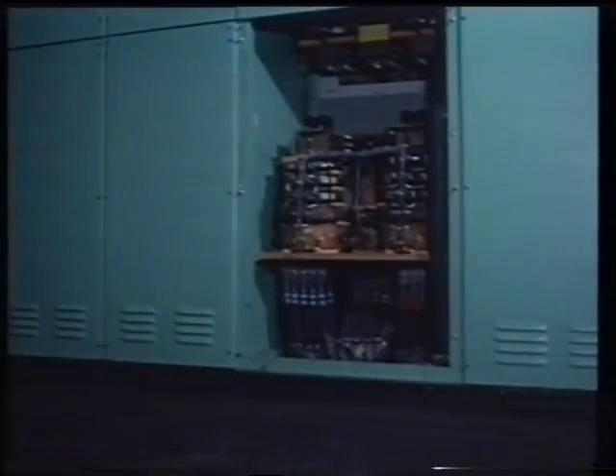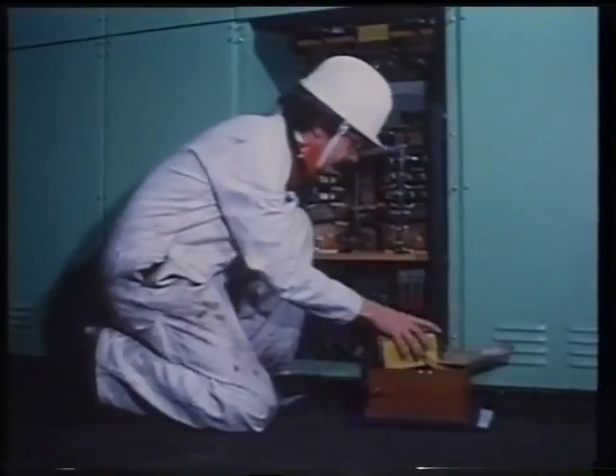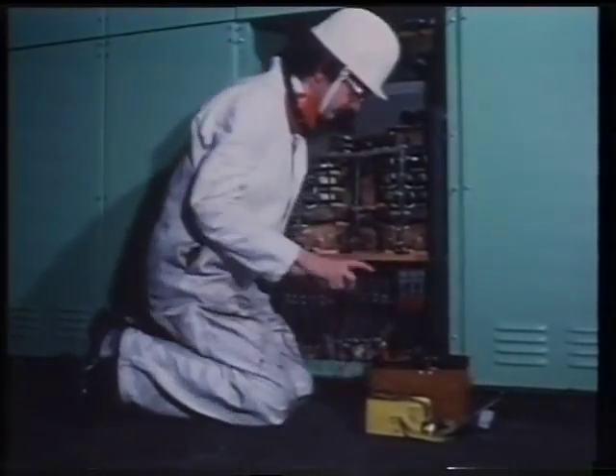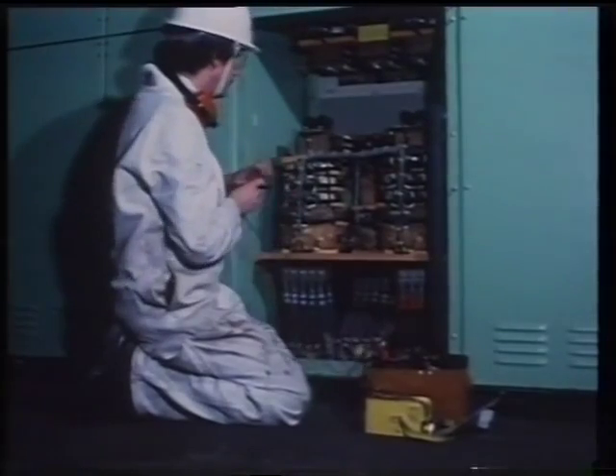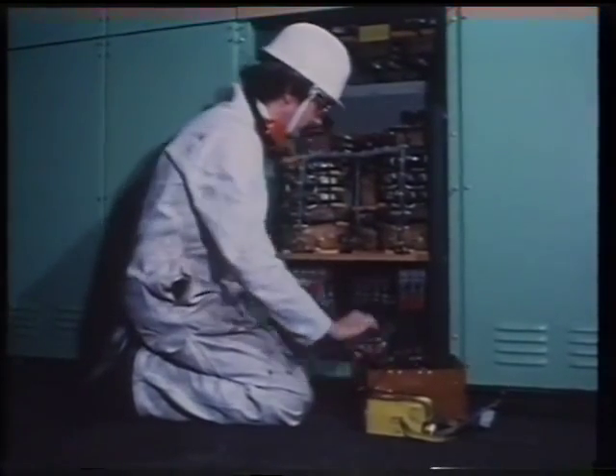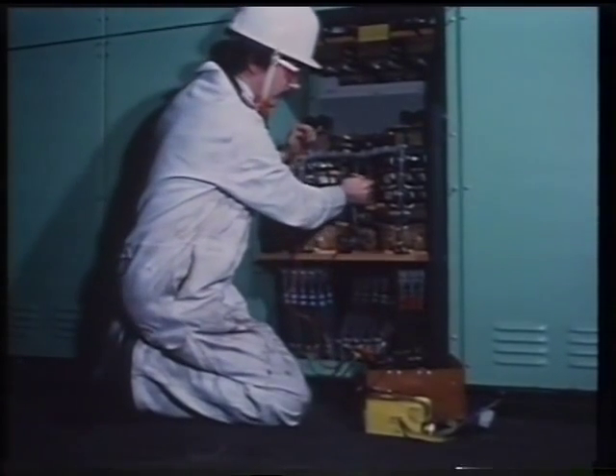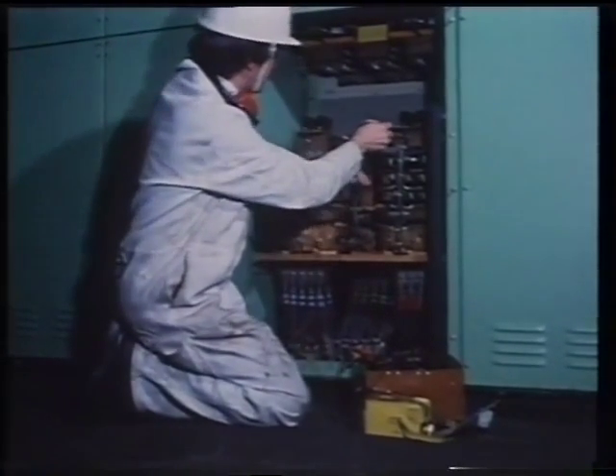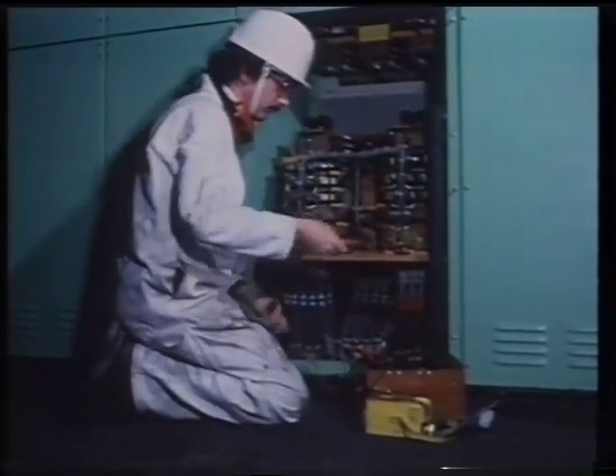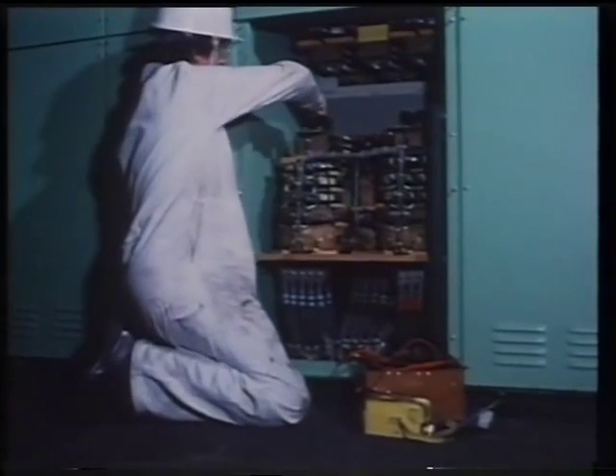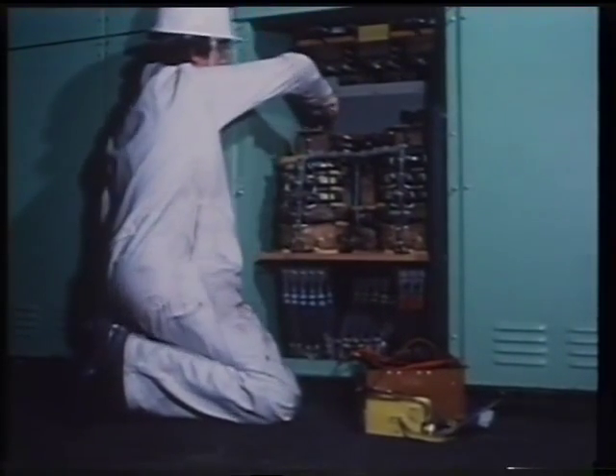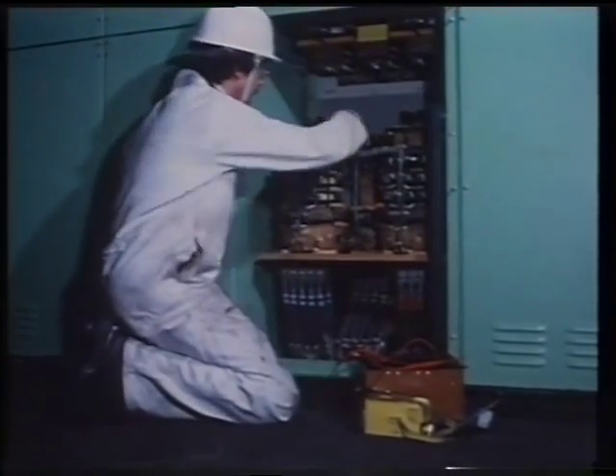Most electrical superintendents and chief engineers like to leave the AC generators and their voltage regulators well alone in normal circumstances, but occasionally some tests and repairs have to be carried out. Insulation resistance and continuity tests of the alternator windings and feeder cables can be conducted from the incoming side of the generator breaker at the switchboard. Remember always to use a rubber mat for safety when working behind the switchboard. For the sake of measurement accuracy, the instrument fuses, the indicator fuses, and the control circuit fuses must be removed.